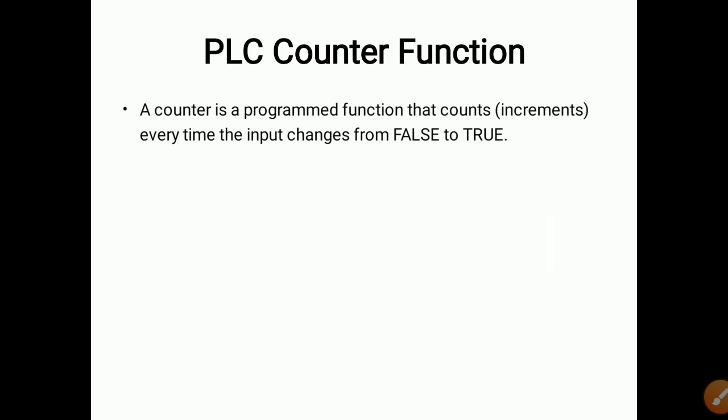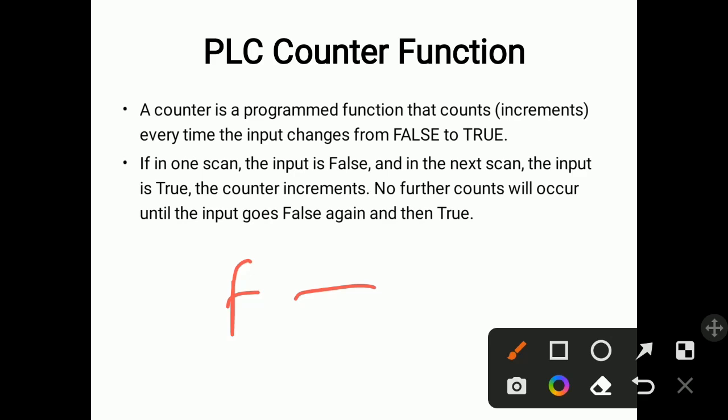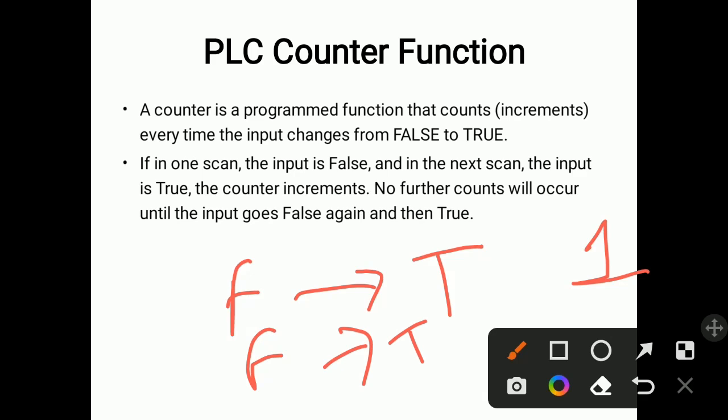Now we will study the PLC counter function. A counter is a programmed function that counts or increments every time the input changes from false to true — this transition is one count. So however many times the input changes from false to true, the counts are incremented. In the next scan when false converts to true, your count becomes two.